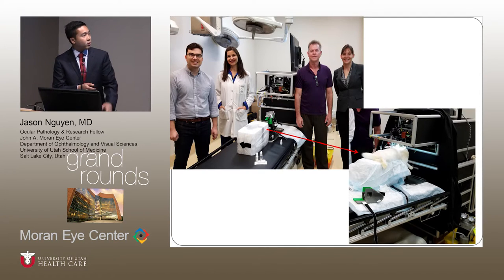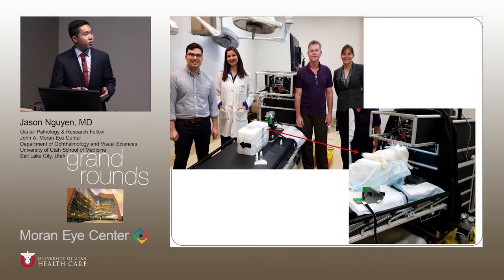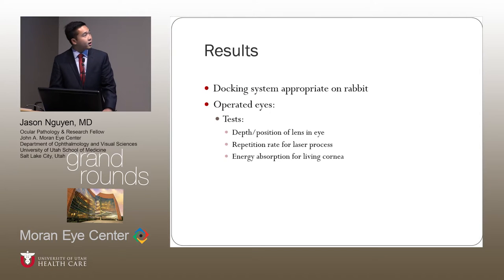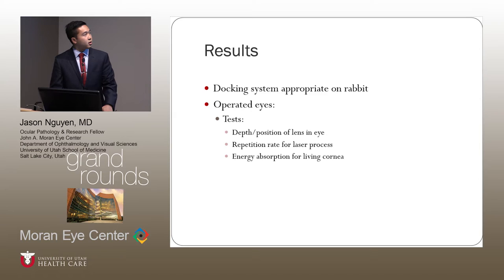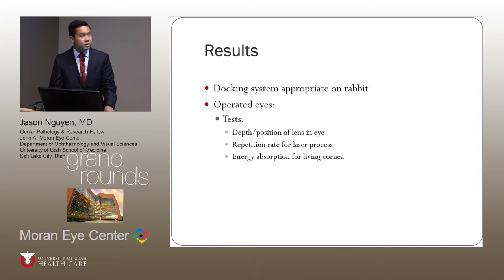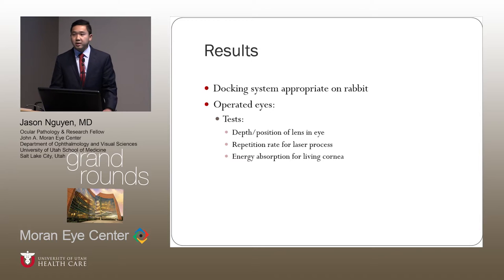With this picture I wanted to show the setup — essentially just positioning the rabbits. We were trying to test the docking of the laser system to the actual rabbit eye. What we found was that the docking system was very appropriate on the rabbit; it took quite a while but we did eventually figure it out. The company was able to determine some of the parameters they needed for future tests — the depth position of the lens in the eye, the repetition rate for the laser, and how much energy absorption was taken out by the cornea. From here, we plan on experimenting with more long-term biocompatibility of the treatment and seeing how well the treatment does in living tissue.